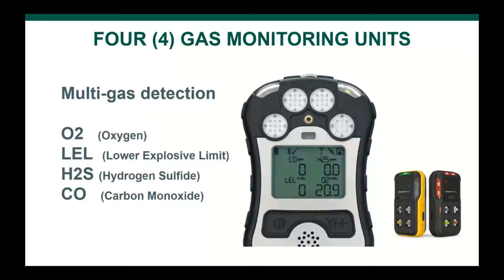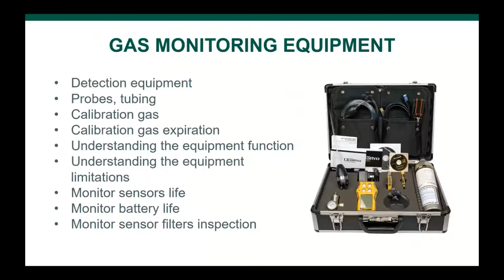Now, is just this monitor sufficient for me to do my required monitoring? Well, no, you need more equipment than that. Because remember, you're going to need tubing, you're going to need probes to be able to test the air inside of the confined space at different levels because of the behavior of gases. You have to have calibration gas. You have to make sure that the calibration gas is not expired. It does have a shelf life.